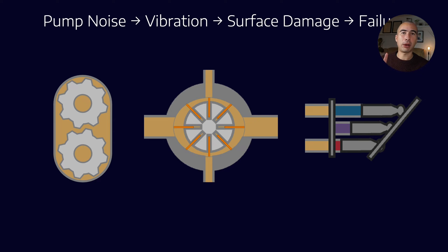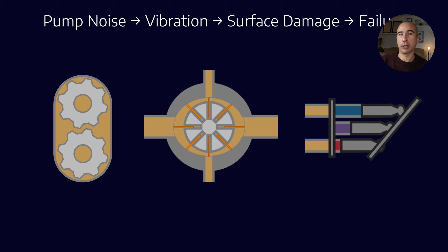Now just having pump noise itself is not necessarily a sign that you have micro-dieseling because it could really be two things. It could be cavitation which happens on the suction side or it could be micro-dieseling which happens on the discharge side. So let's talk a little bit about what micro-dieseling is specifically and then we'll be able to see how it differs from cavitation.